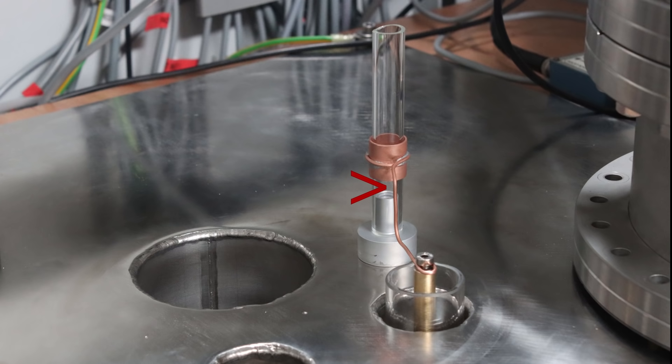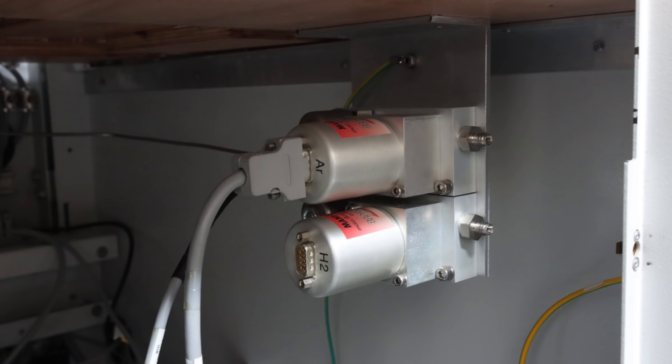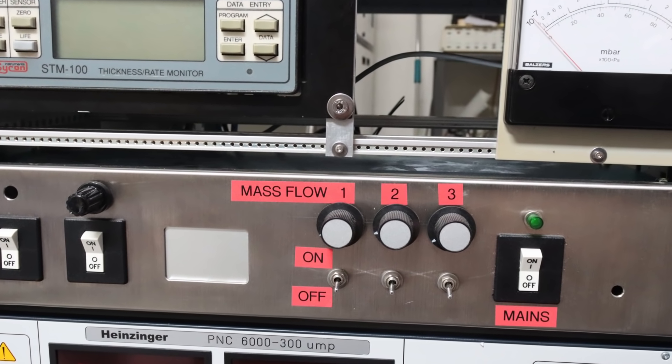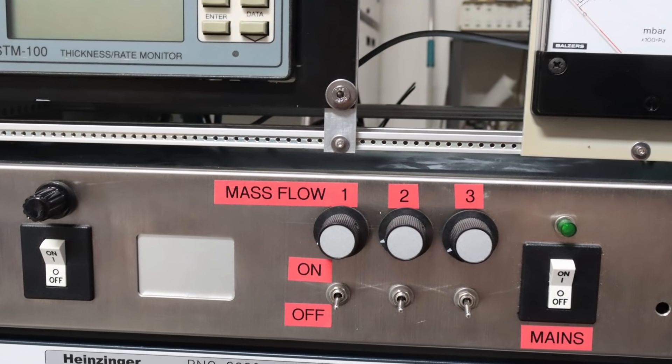The plasma is made from air that is led into the chamber at a very low flow rate. I used a mass flow controller salvaged from the Balzers unit for this. I also made a control unit to regulate the flow through the mass flow controller. This is what the plasma looks like in operation, it is sort of a bluish pink due to the presence of mainly nitrogen and oxygen. It seems to work very well for removing organic contaminants in just a few minutes.